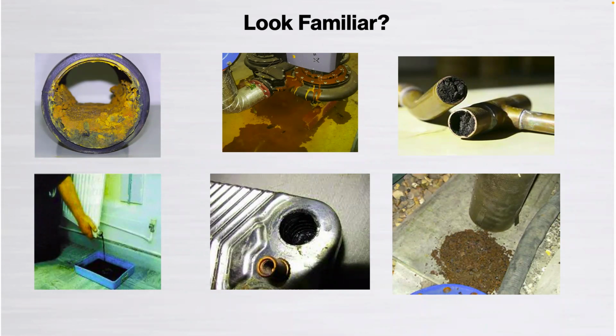The bottom middle picture shows a small domestic size plate heat exchanger. It's common practice now to protect new plant and equipment in a refurbishment, whereby it's been added onto an existing, let's say, school. They may look to use a plate heat exchanger to protect the new equipment. But of course, both sides of that plate heat exchanger need to be well protected, and we need good, clean, chemically and microbiologically controlled water to pass through there.